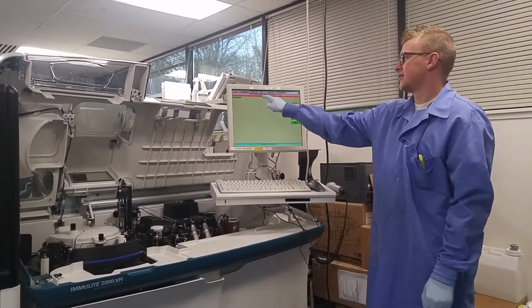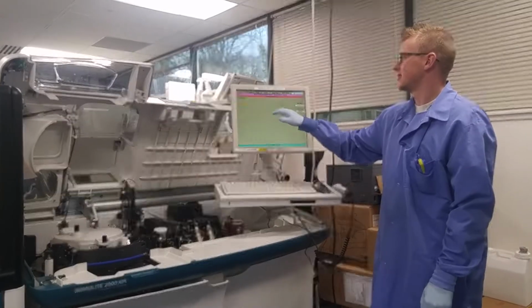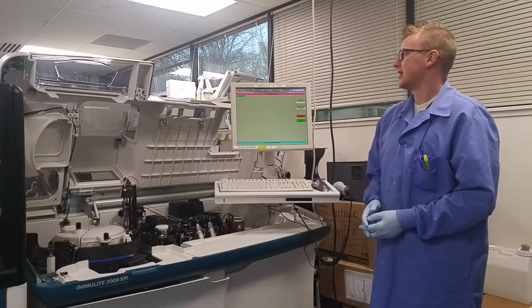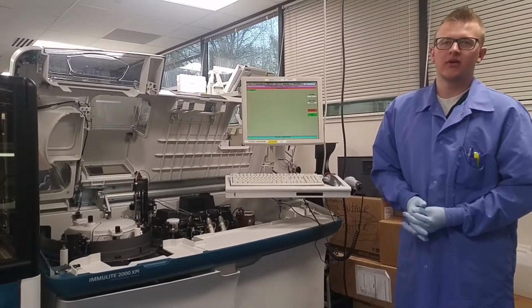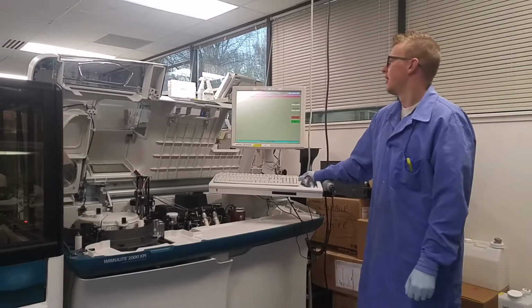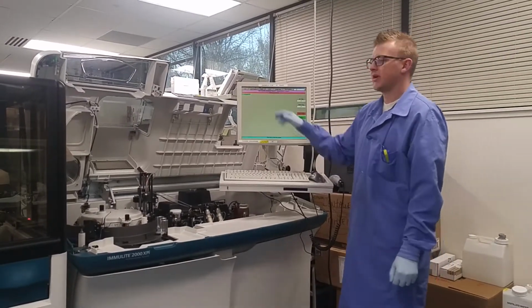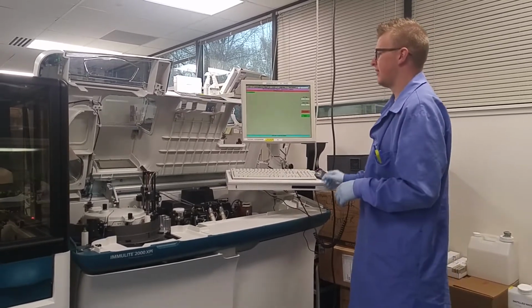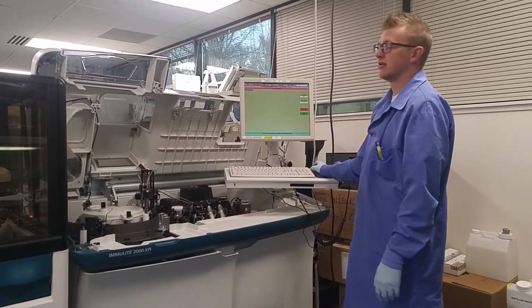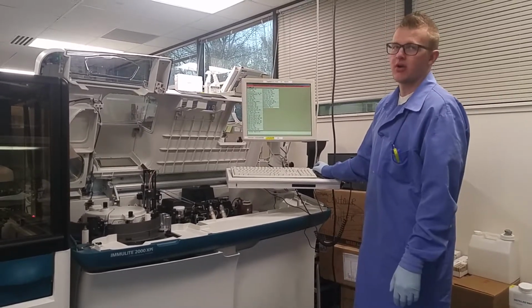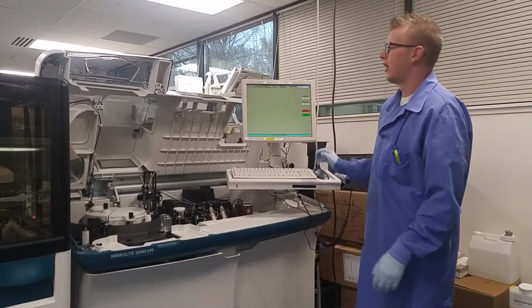This message here says initializing ramp tables. It will switch to homing all motors. Once the process is done, it will say program complete, and then we'll go on to the next step. So now message is switched to homing completed, so we know that our test system is back to its default ready setting, and everything is aligned. So now go back to load program, and we're going to select Clot Prime. We're going to run that program.